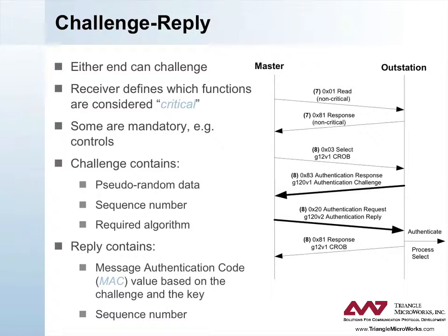In this example, the master sends an authentication reply object in reply to the challenge. Since the DNP3 terminology of request and response still applies, this reply object is transmitted using an authentication request function code. This may be confusing, but it helps to remember that in DNP3, masters always transmit requests and outstations always transmit responses. The authentication reply object contains the MAC, which the outstation will compare to the one it calculates internally.